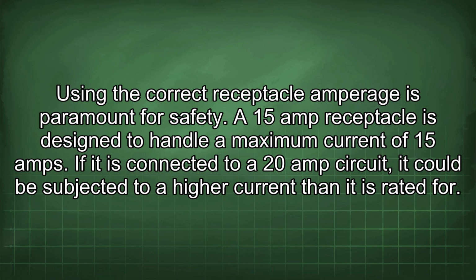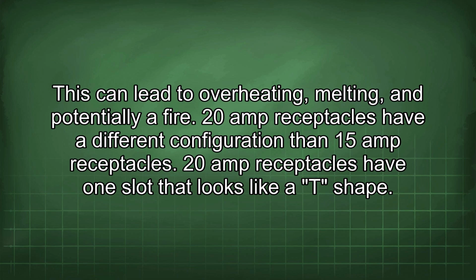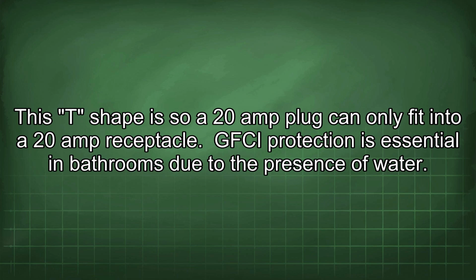Using the correct receptacle amperage is paramount for safety. A 15 amp receptacle is designed to handle a maximum current of 15 amps. If it is connected to a 20 amp circuit, it could be subjected to a higher current than it is rated for. This can lead to overheating, melting, and potentially a fire. 20 amp receptacles have a different configuration than 15 amp receptacles. 20 amp receptacles have one slot that looks like a T-shape. This T-shape is so a 20 amp plug can only fit into a 20 amp receptacle.